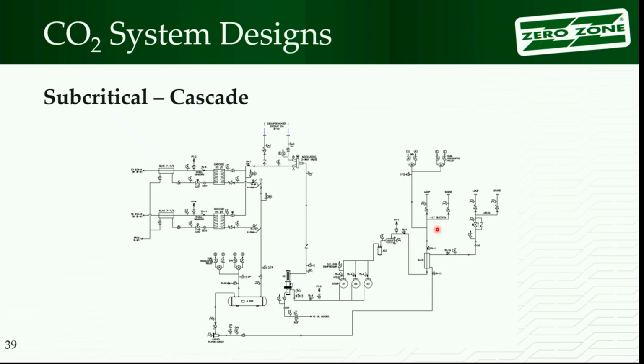The other room had a better display. That little oddity is an indication of one of those ball check valves. So it's a check valve built into that ball valve, and it's checking in this direction. So if the pressure downstream of the valve drops, it's going to let something in from upstream of the valve. So if I close those valves and think I'm ready to service, and I start trying to bleed the pressure out of there, I'm going to be surprised because I never get to bleed the pressure out. It just goes on and goes on and goes on, and it's not because the valves are broken, it's because that valve was set up as a ball check.